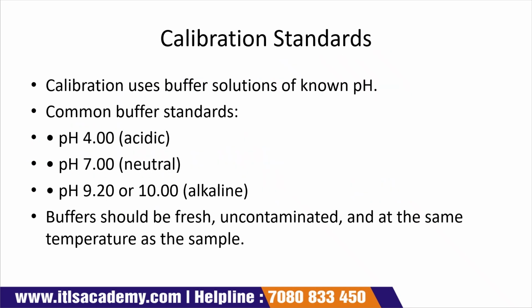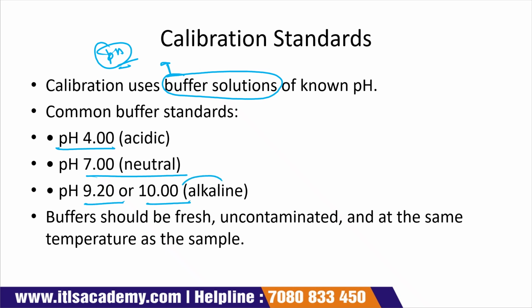Now, calibration standards. For the calibration of the pH meter, we require a buffer solution, and the pH of that buffer solution will be known. Here we can use three types of common buffer solution. pH 4 is for the acidic, pH 7 is for the neutral, and pH 9.20 or 10 is for the alkaline. The buffers that we prepare for the calibration should be fresh, uncontaminated, and at the same temperature as the sample. If it is contaminated, then it will give an error.